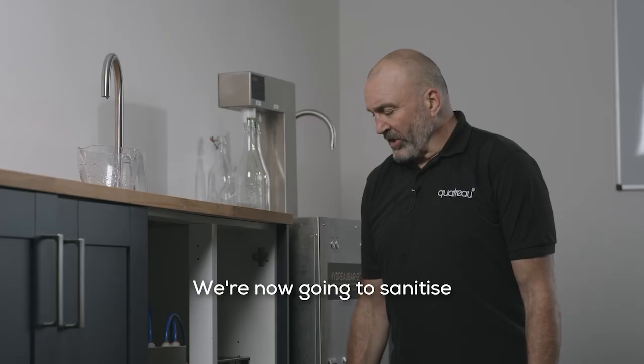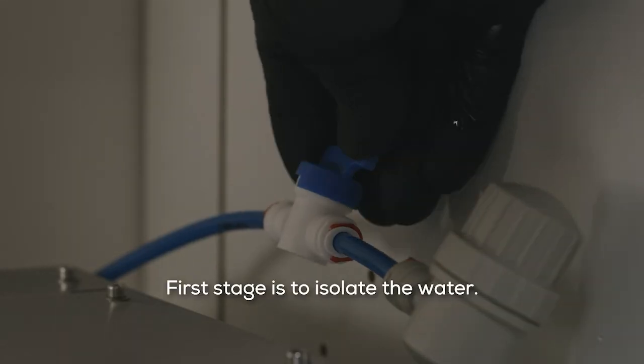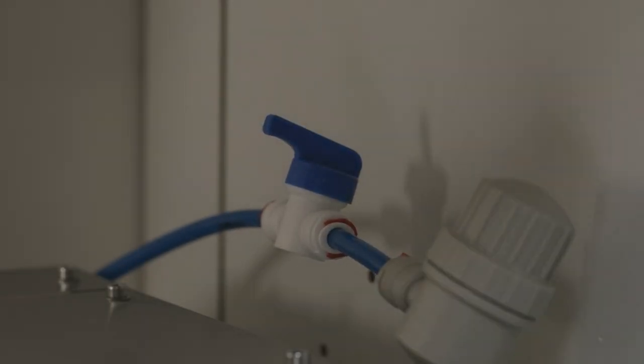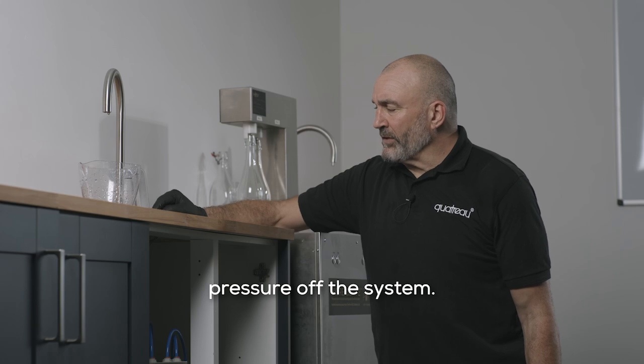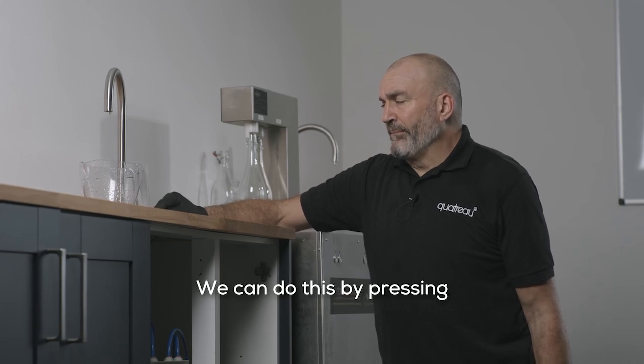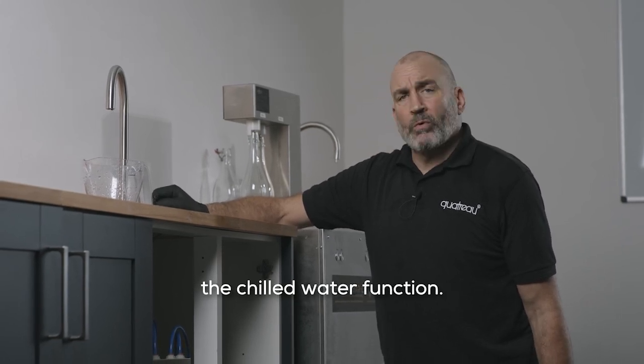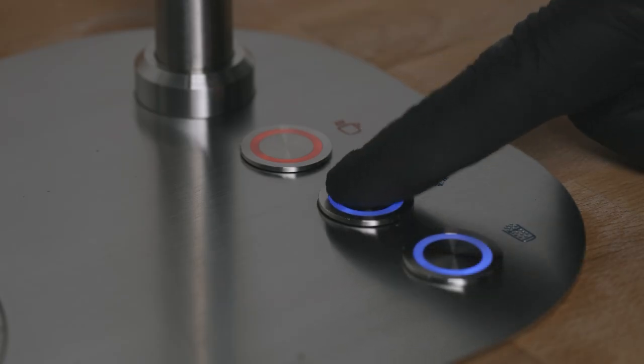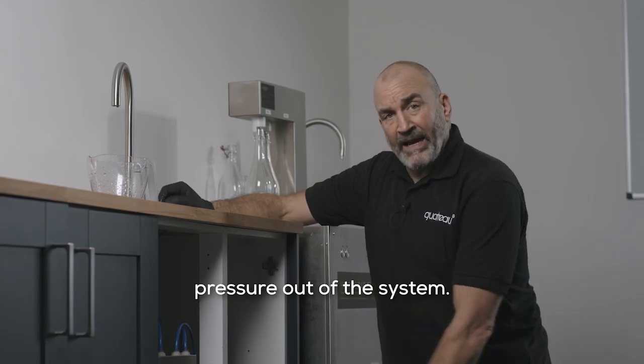We're now going to sanitize the Quatreau SmartTap system. First stage is to isolate the water. We now need to take the pressure off the system. We can do this by pressing the chilled water function. That just takes any pressure out of the system.